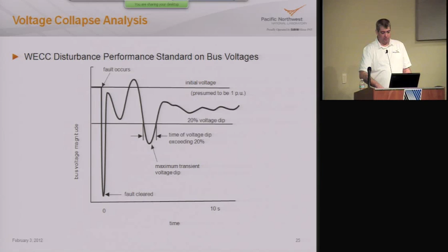So we shed the load and let it recover. This is a particular location that has a voltage stability issue. And then we reconnect the load. It does drop below 0.8 per unit. At that point, the undervoltage protection would start triggering, but that's set up on a time delay. It has to be below 0.8 per unit for a certain amount of time in order for it to actually trip and start things that we don't want to happen. And the voltage came back up within that time period. So we tested this case, and we found that, at least in that scenario, it was robust.